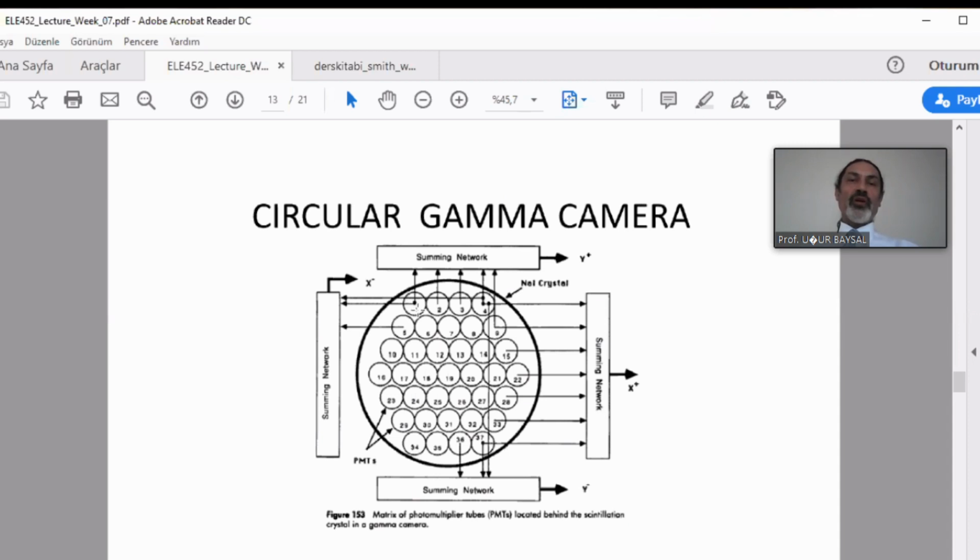So in that square, if a gamma ray hits the sodium iodide crystal or scintillation crystal, that high energy gamma ray produces visible light photons, and the number of photons on the phosphor screen creates electric current, or in a charge coupled device, electric voltage. So voltage or current is proportional to the number of visible light photons coming into the area.